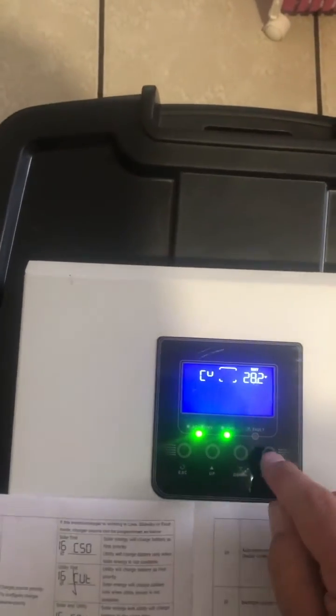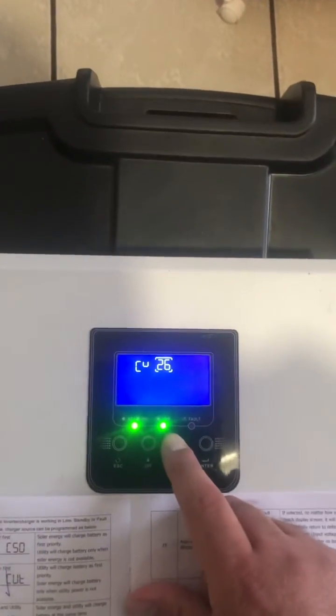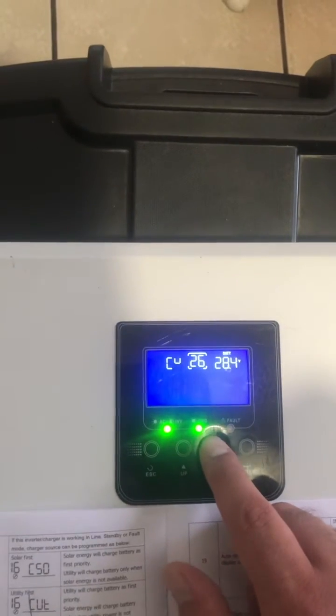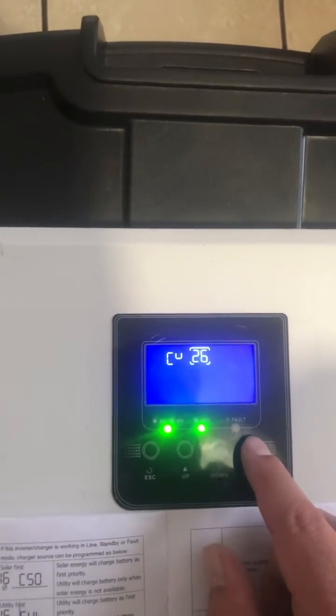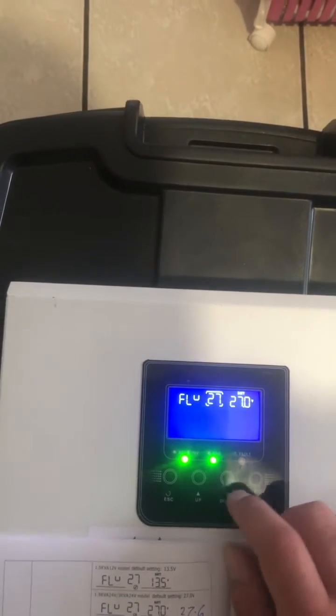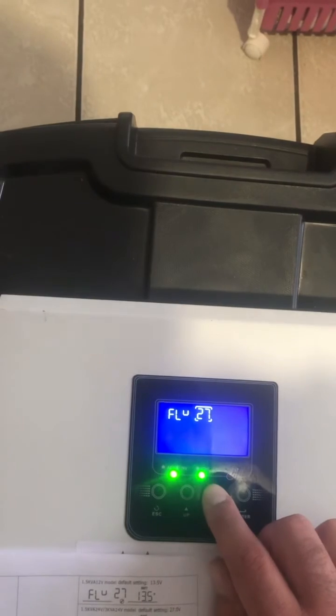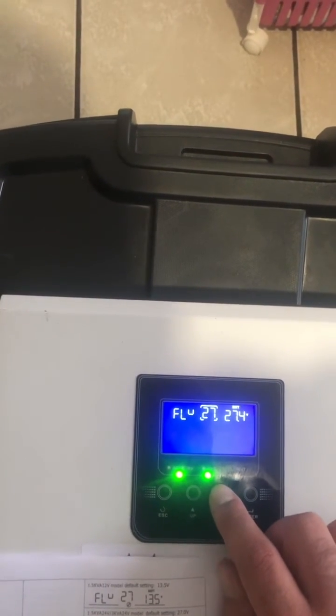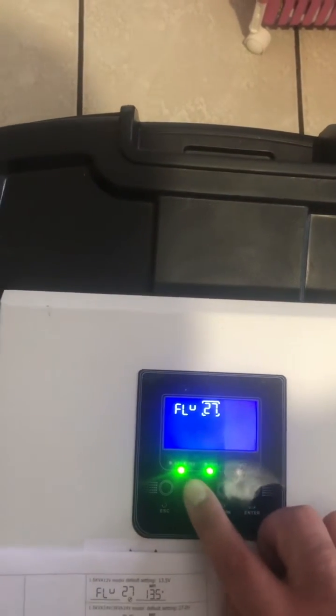Number 26, we'll want to set to 28.6, so press down 4 times, press enter, back to the number, down to number 27, we'll want to set to 27.6, press enter, all the way down to 27.6.